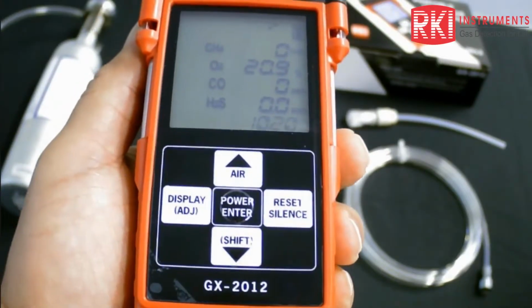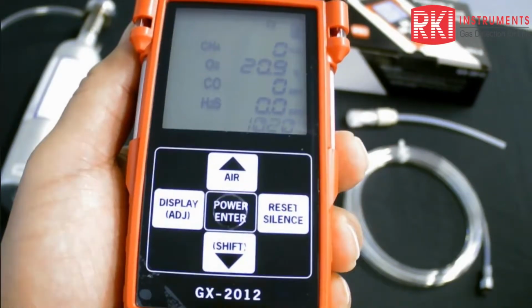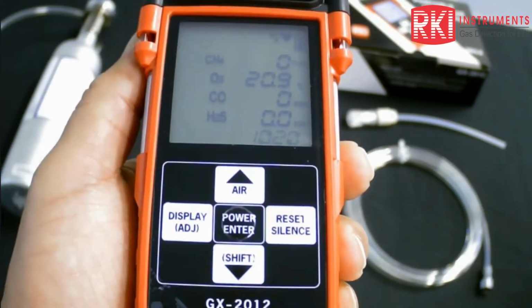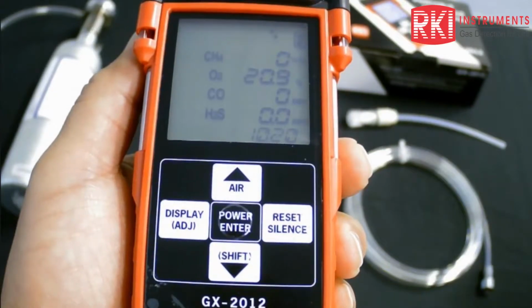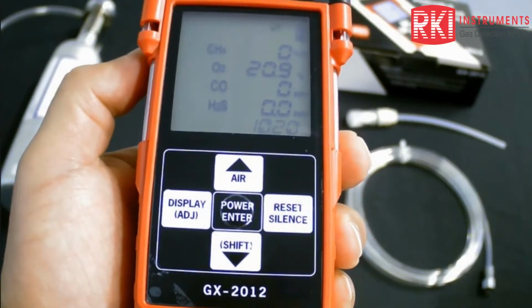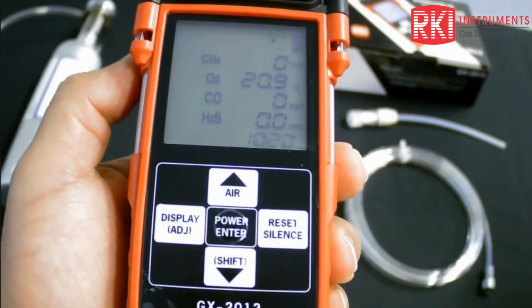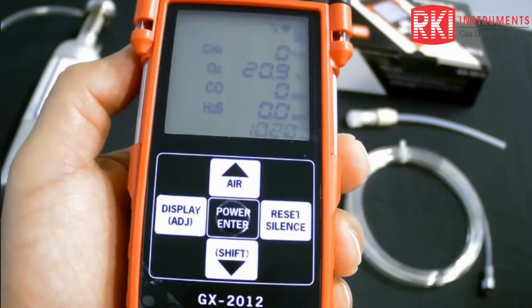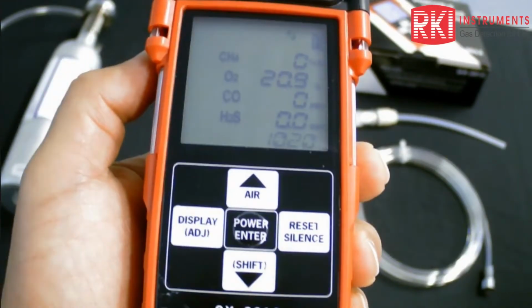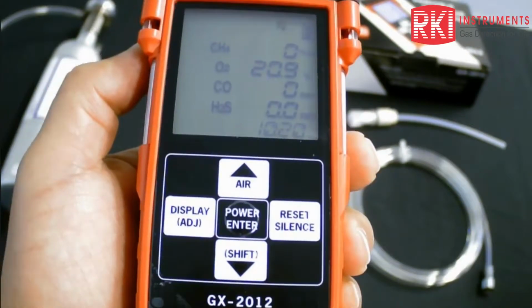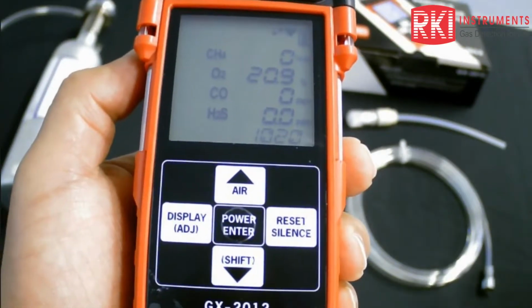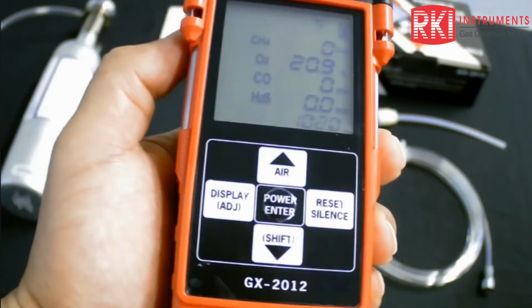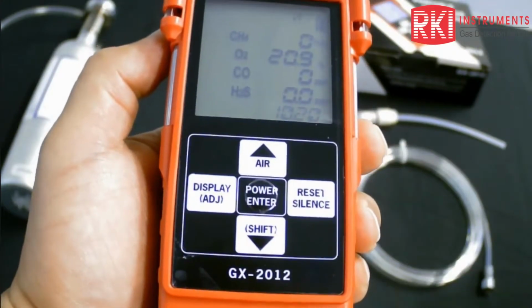And again, this is an auto-ranging unit, so you'll never see that 5th sensor on board as a 5th line item on the display. That LEL line item, the CH4, again, that auto-ranges appropriately from %LEL to % by volume. So you're always only going to see 4 gases or 4 sensors on the display at any time. Okay, just to clarify that one more time.